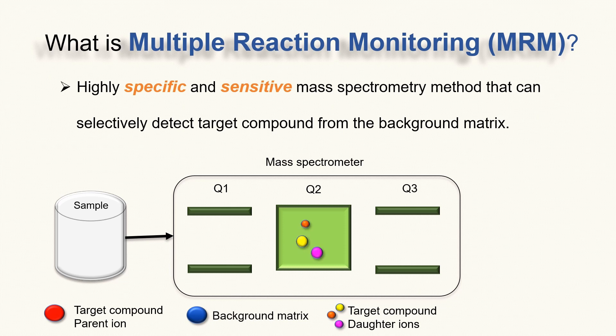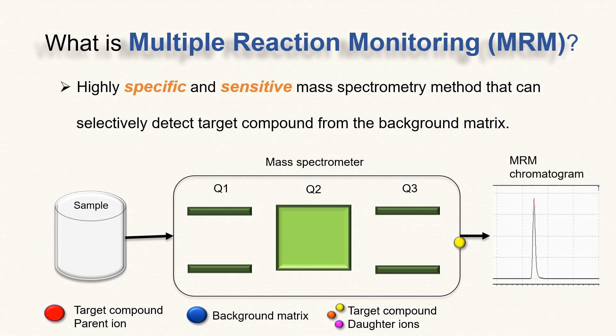Then, collision-induced dissociation takes place in Q2, and the parent ion is fragmented into several daughter ions. Finally, Q3 is set in a way that only the selected daughter ion can travel through Q3 to reach the detector. The final signal is displayed as a peak in the MRM chromatogram.